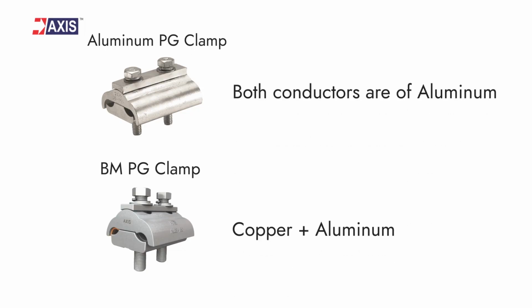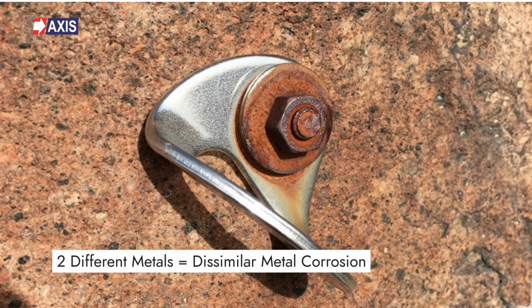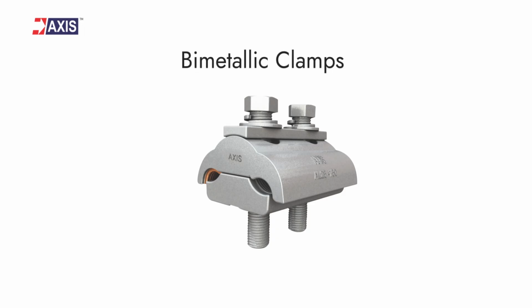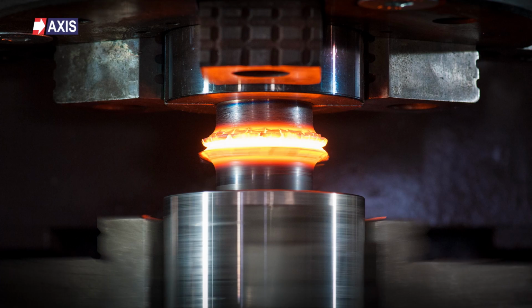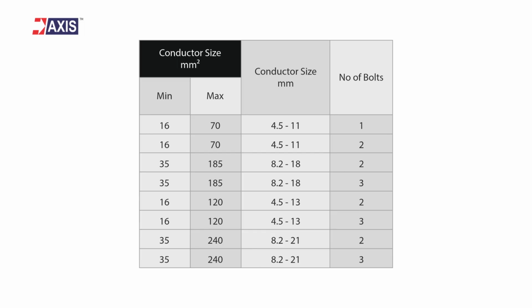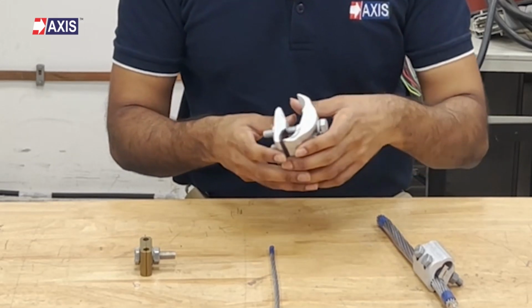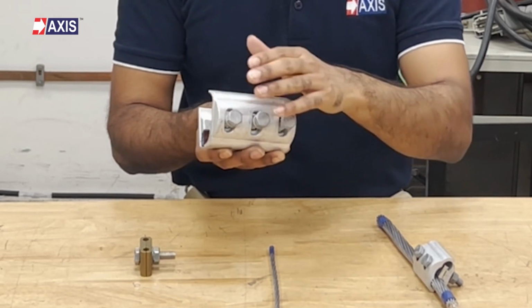But if one of them is made out of copper, then you need a bimetallic PG clamp, because when two different metals are in contact for a long time, they can cause dissimilar metal corrosion. Bimetallic clamps help solve this problem by having a copper side of the clamp. This copper to aluminium joining of the clamp is done using friction welding. As a result of the friction welding, dissimilar metal corrosion is avoided. Bimetallic clamps also come in different sizes and bolt types, just like the aluminium clamps. This one here, as you can see, is a 3-bolted clamp.